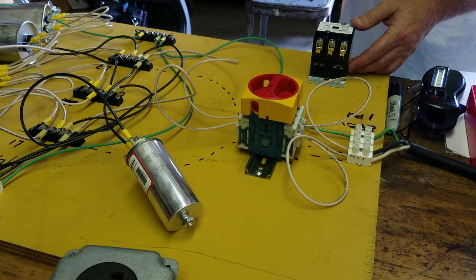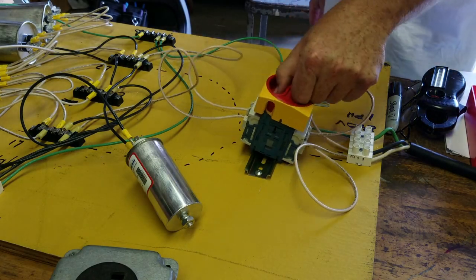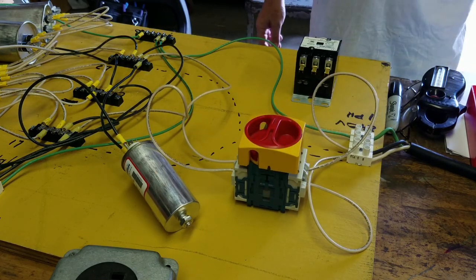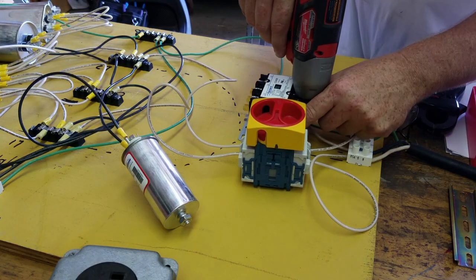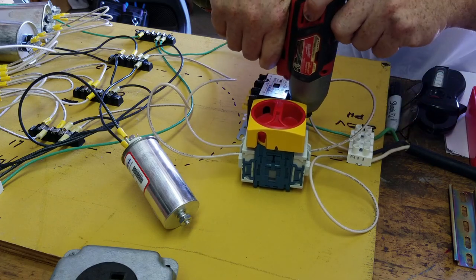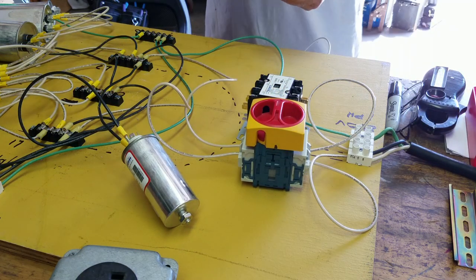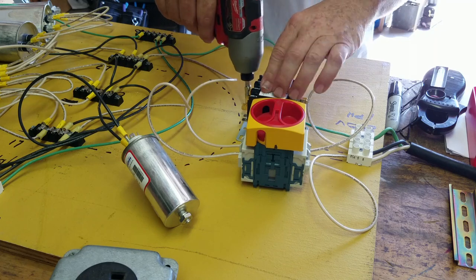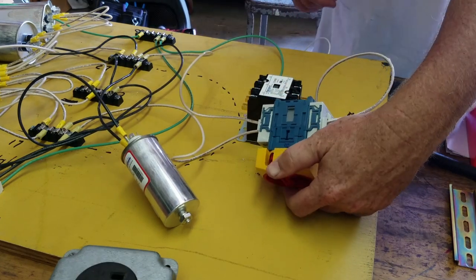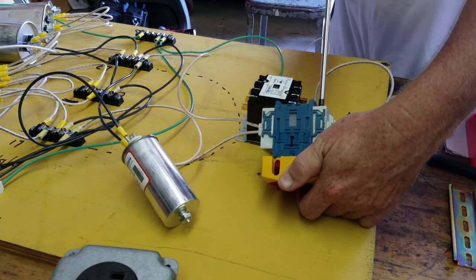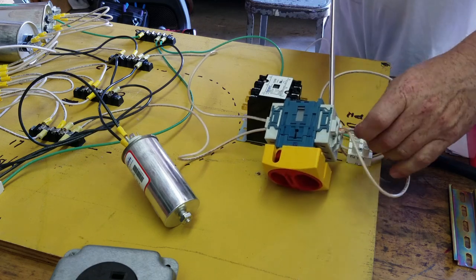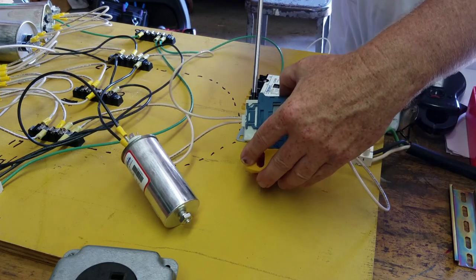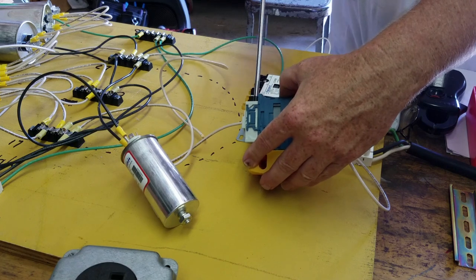The next component I added was a magnetic motor starter. And this is basically just a big relay switch. The one I'm using here is a three-pole motor starter. I could have actually used a two-pole starter. And the fact that it's called a motor starter is kind of a misnomer. Again, it's really just a big relay. The initial wiring is really simple and just goes in line where the barrel switch was. It protects me in the instance of a power outage.